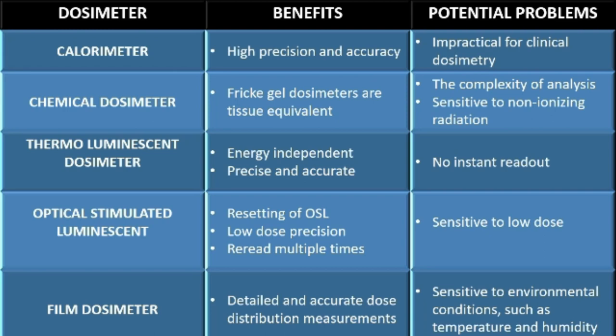Thermoluminescent and optically stimulated luminescent dosimeters are both reusable and energy independent, and can be used as personal dosimeters, but they are unable to give instant readings. Film dosimeters can give accurate dose distribution, but these films are sensitive to environmental conditions including temperature and humidity.